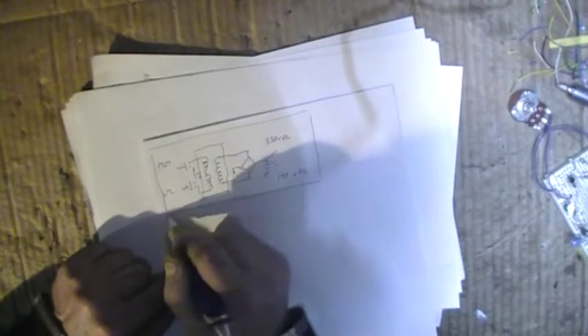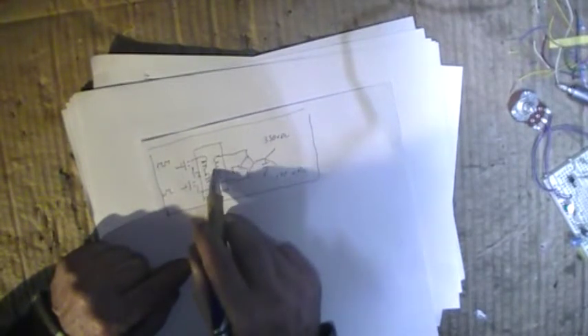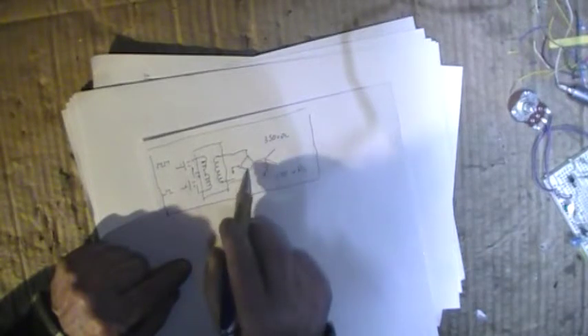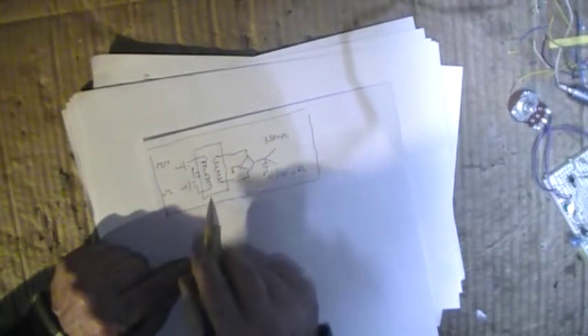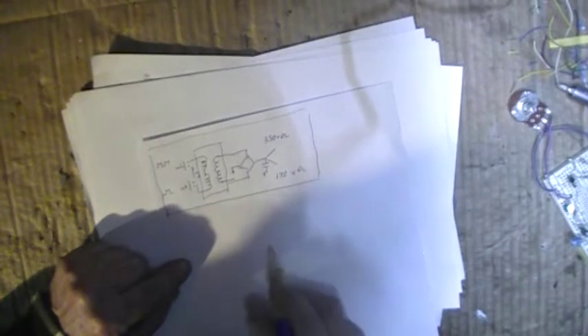170 volts DC. Now this is what I call the first stage of the inversion process. A high frequency inverter, simply chopping the battery voltage, 12, 24, 36 volts, whatever it happens to be, chopping it up into a high frequency, passing it through a transformer, rectifying it into 350 or 170 volt DC.